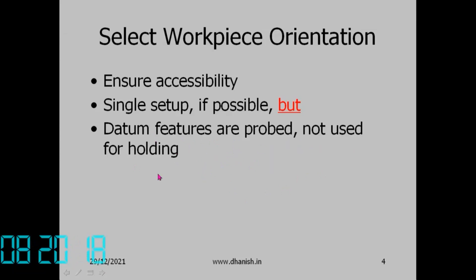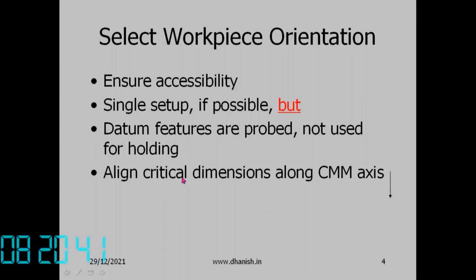Datum features should be probed, not used for holding — if you hold on the datum surface, you cannot access it for probing. Tightening nuts and bolts should not be on the datum surface. Also, align critical dimensions along the CMM axis, since maximum accuracy is obtained along the axis.